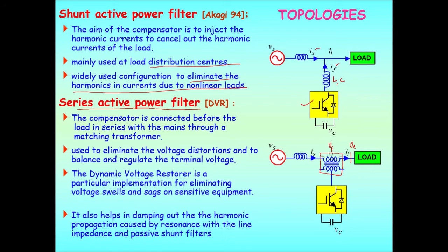Series active power filters, as the name indicates, are connected in series with the load. You can see it here. This is the series connected transformer. The secondary of the transformer is connected in series with the line, and the primary of the transformer is excited by the output of the inverter by way of switching, and hence by using proper filter components we have an output voltage in such a way that the voltage at the load bus is always maintained in the given limits. So this device is called DVR or dynamic voltage restorer.